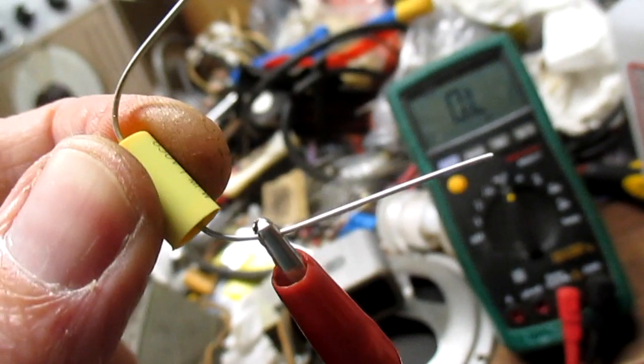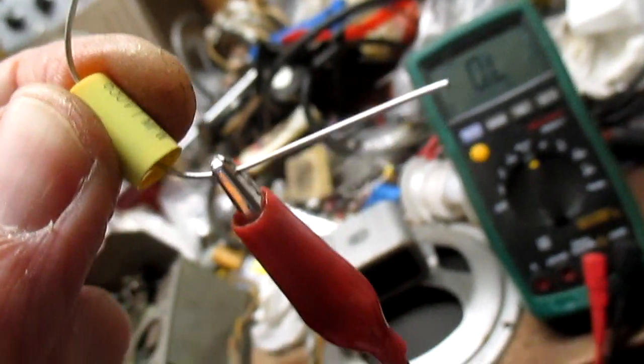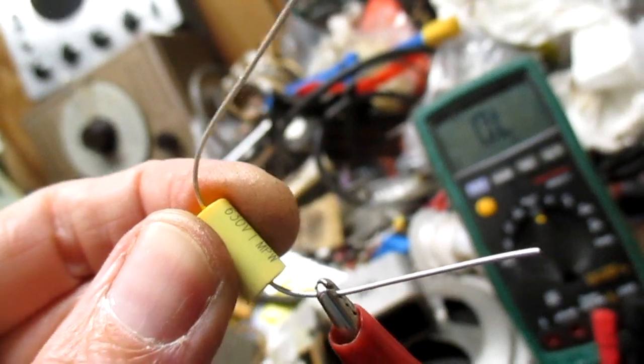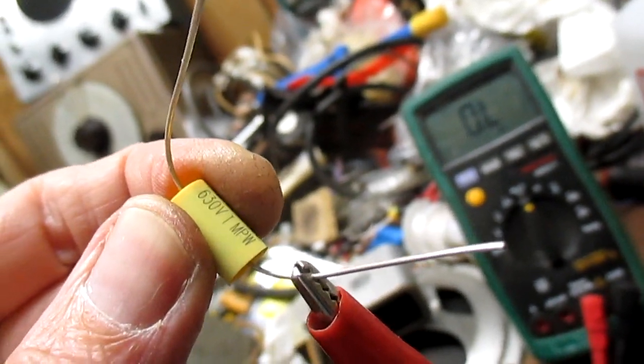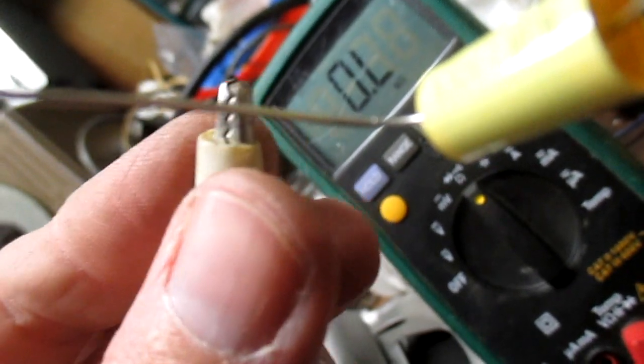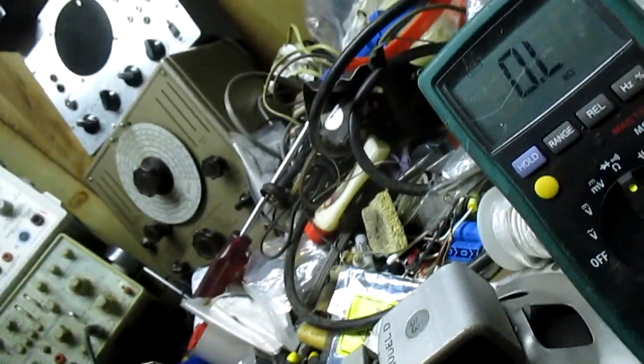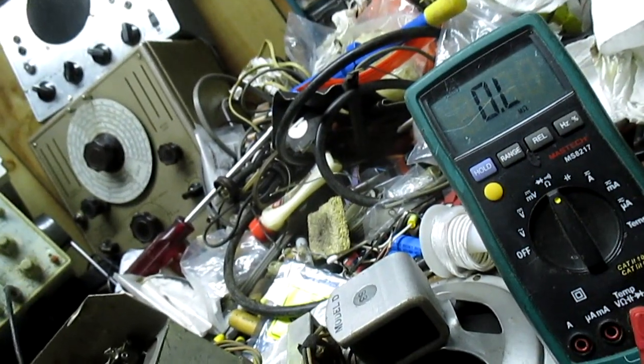Here's a new 0.02 microfarad capacitor, and I'm going to show you how this does on an ohm meter. This is a brand new capacitor. Let's see if I can do this one-handed - I'll touch the meter lead with the other hand. See, it's so quick the meter doesn't even have time to react to it. So that's what a new capacitor should read.